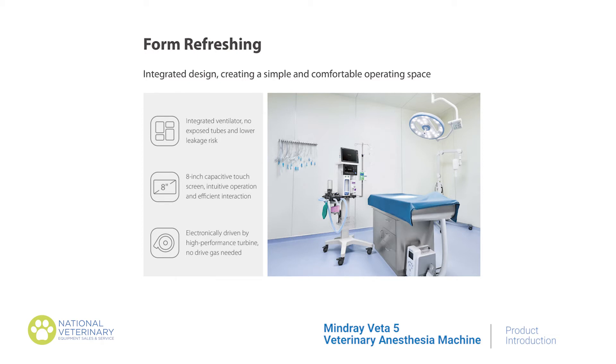Proper ventilation is provided by the Veta 5's smart presets. Spontaneous breathing is supported with the auto-synchronization mechanism. The Veta 5 provides apnea ventilation, ensuring no respiratory depression.